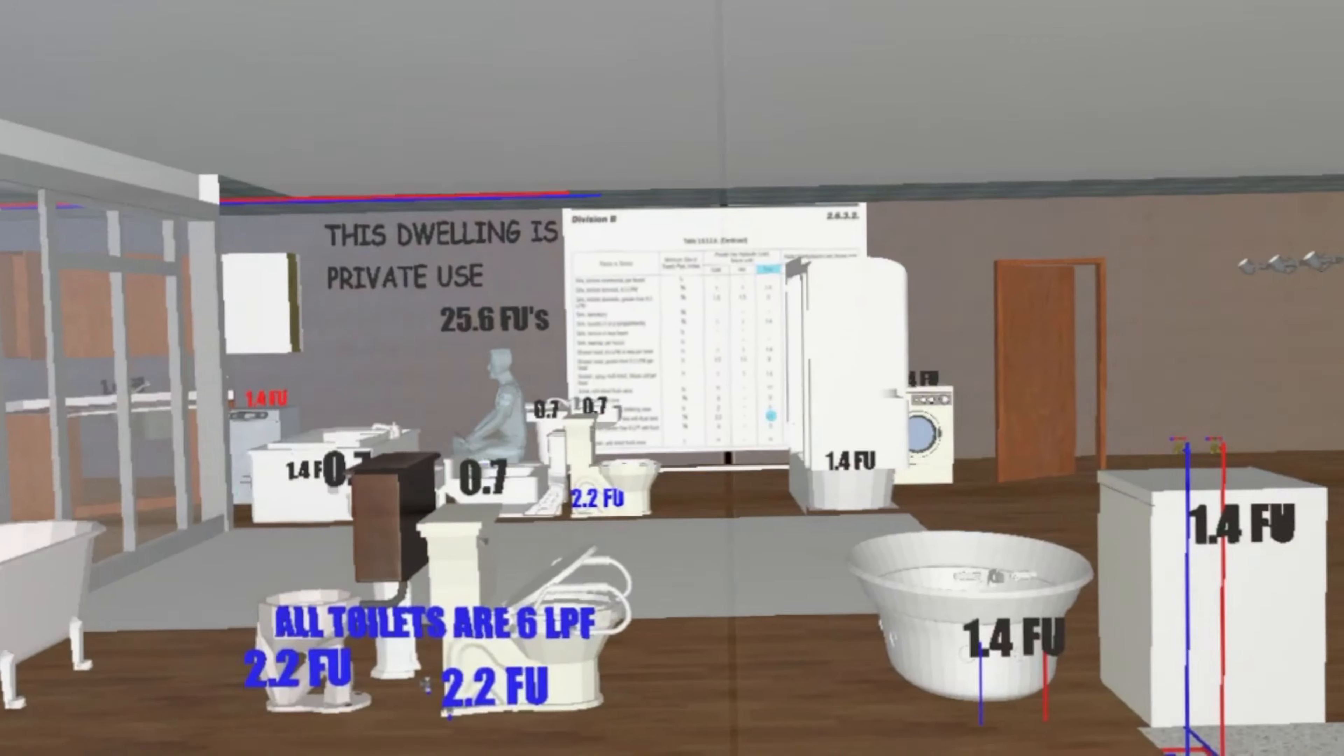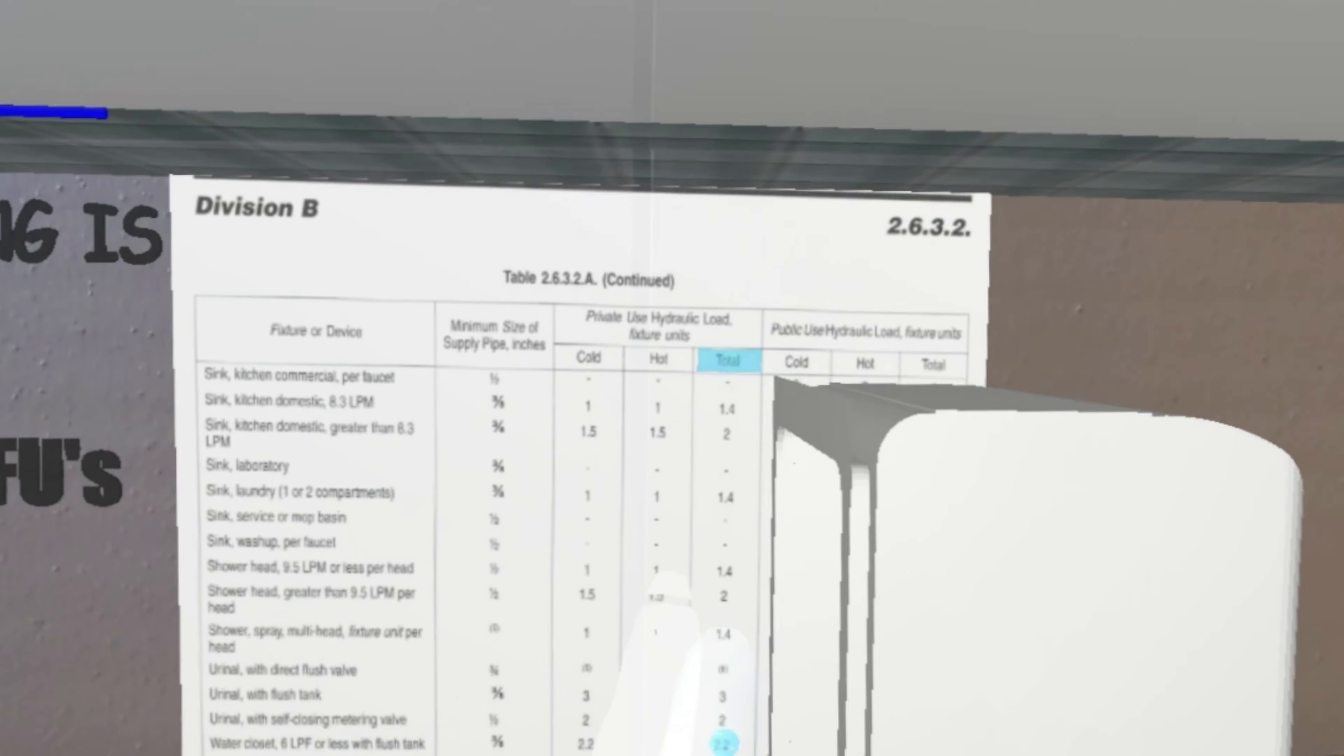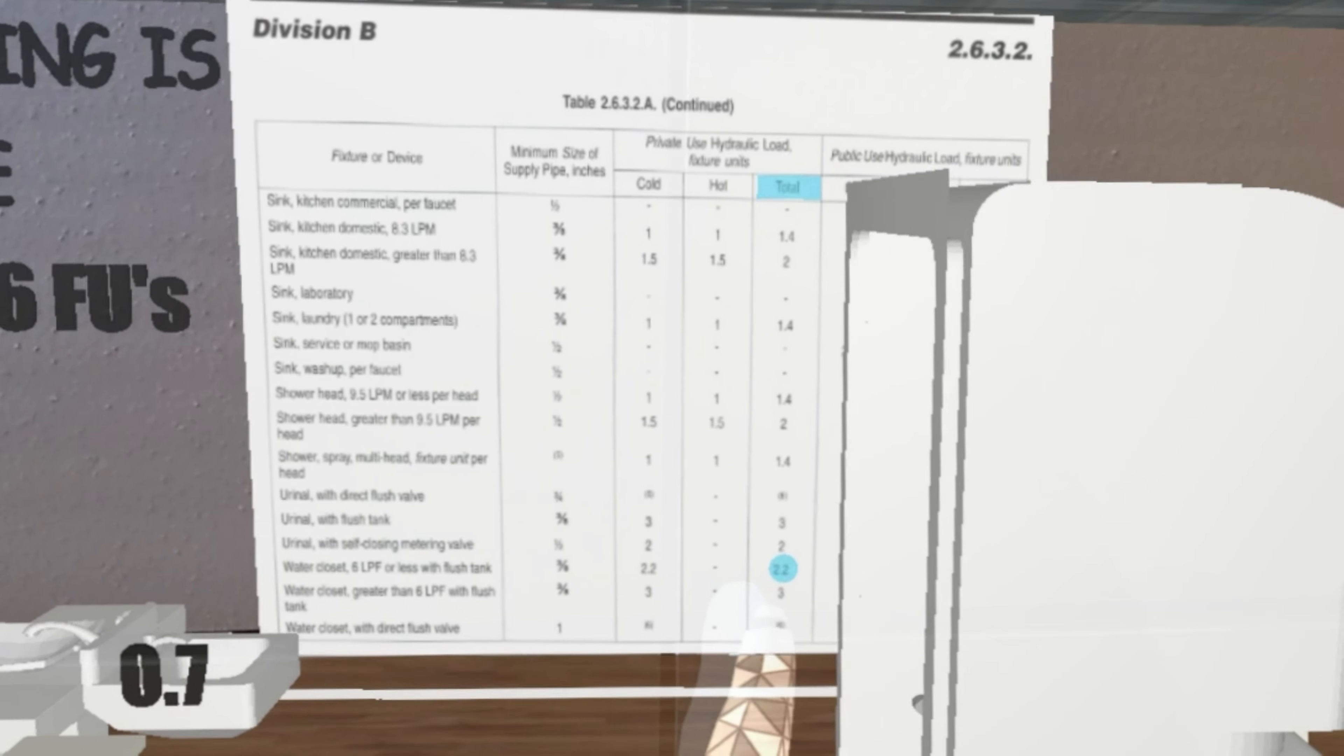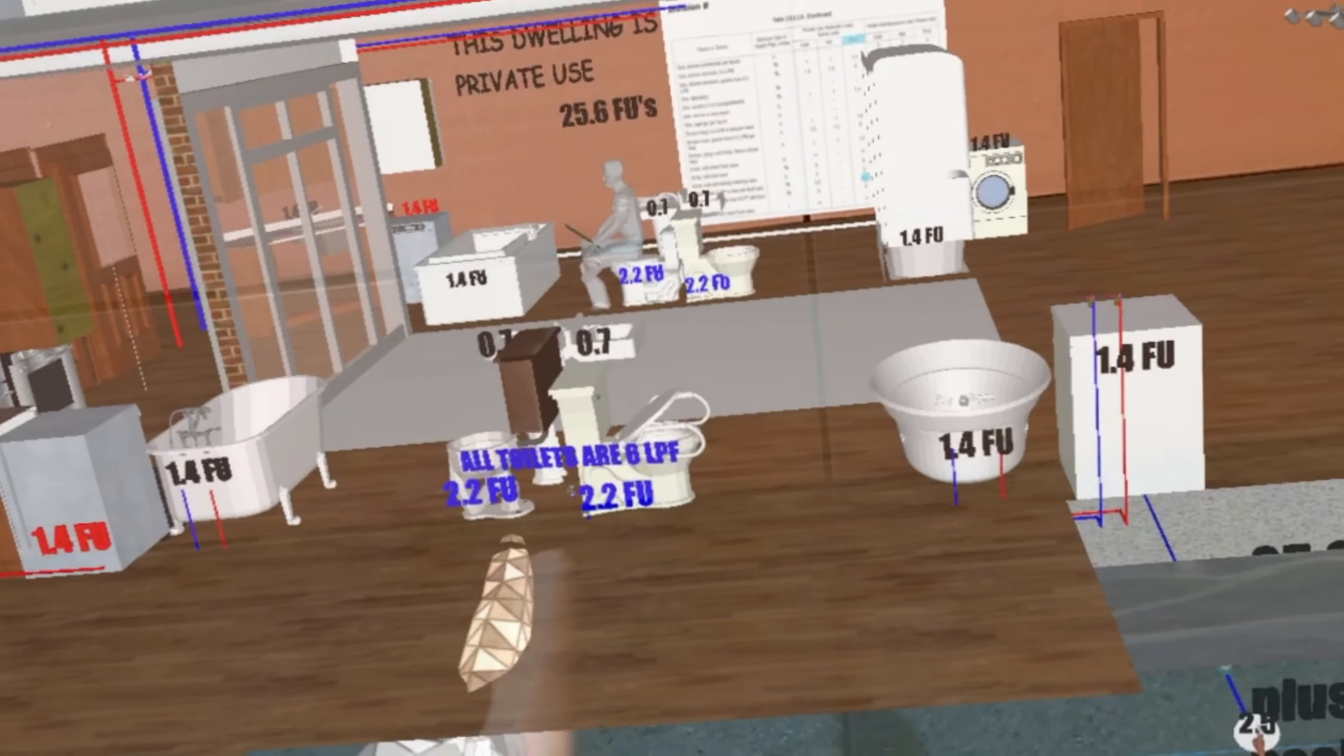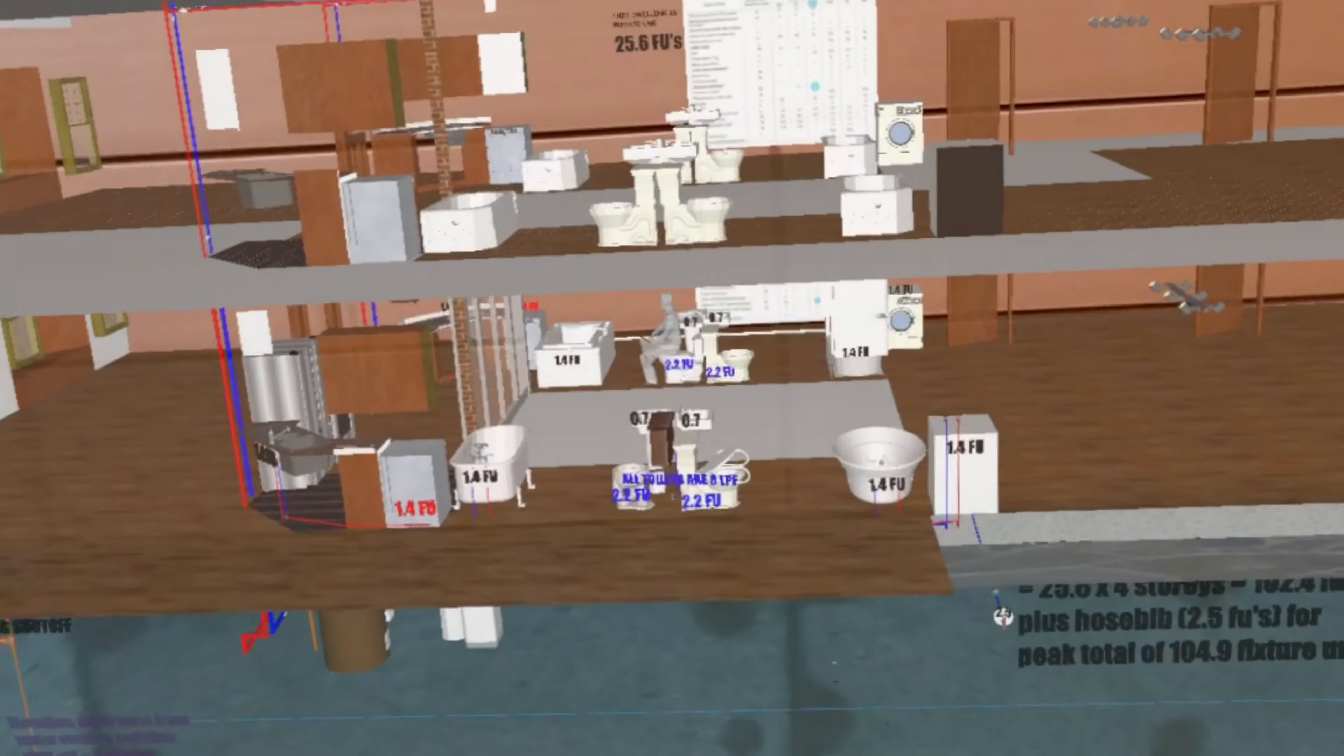And how do you know what these fixture units are? Well the table is on each floor here. So if I look here, this is the table I look at in the code book that tells me all the fixture unit loads. So there is the water closet, six liter per flush, it's 2.2 fixture units. So that's what this is - these two toilets, they're all six liter per flush, they are worth 2.2 fixture units. That's how you add them up.